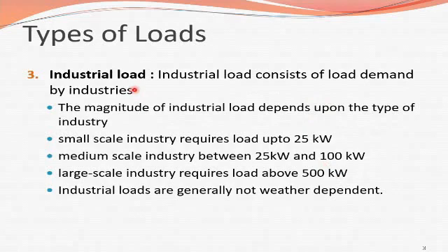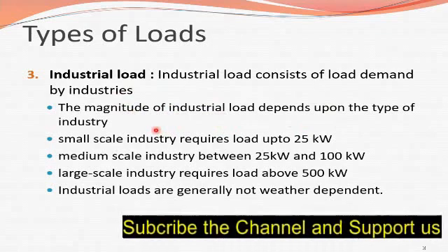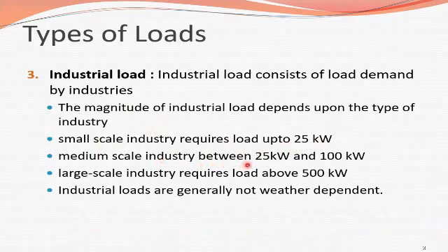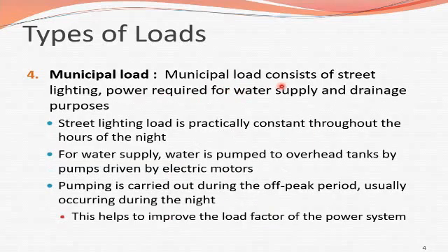The next one is industrial load — the third type. Industrial load consists of load demand by industries. The magnitude depends on the type of industry. Small scale industries require load up to 25 kW, medium scale industries require between 25 kW to 100 kW, and large scale industries require load above 500 kW. Industrial loads are generally not weather dependent.